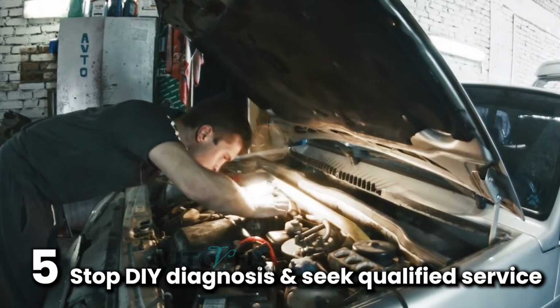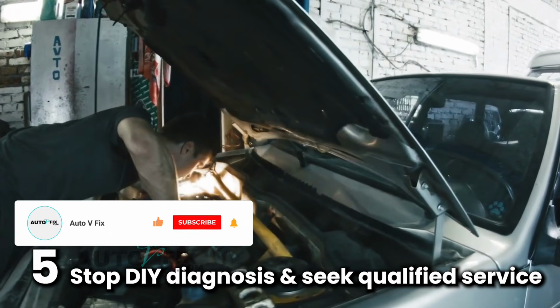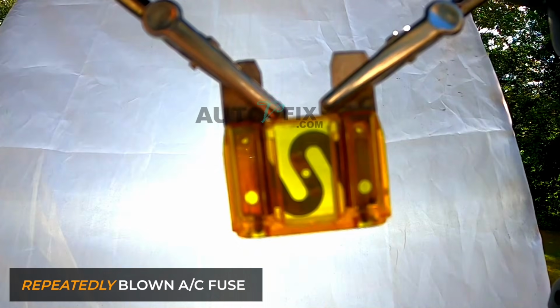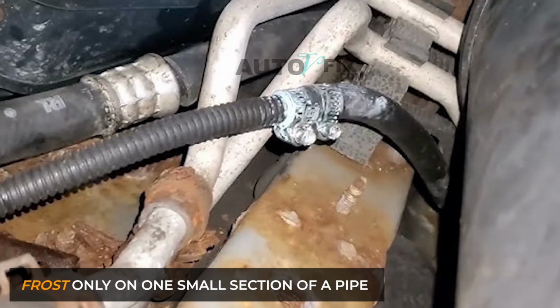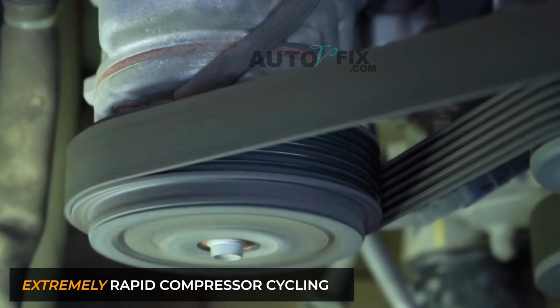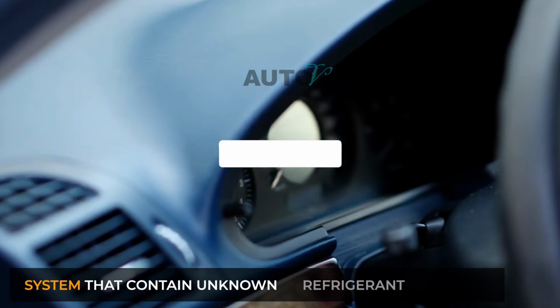Stop DIY diagnosis and seek qualified service if you see oily leakage, damaged AC lines, abnormal compressor noise, a repeatedly blown AC fuse, frost only on one small section of a pipe, extremely rapid compressor cycling, or a system that may contain unknown refrigerant or stop leak.